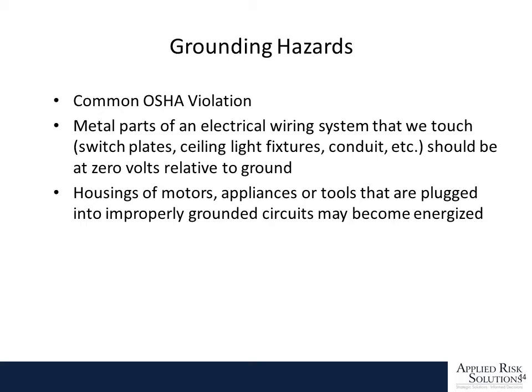Grounding hazards are the most common reason for OSHA citations. Metal parts of an electrical wiring system that we touch, things like switch plates, ceiling fans, stuff like that, should always have 0 volts relative to ground. If you touch something that you should be able to touch, like an appliance, and you feel a tingle, you have a problem. Housings on motors, appliances, things like that should all be 0 volts to ground, and you should not feel any kind of tingling sensation. If you do, something is not grounded properly.